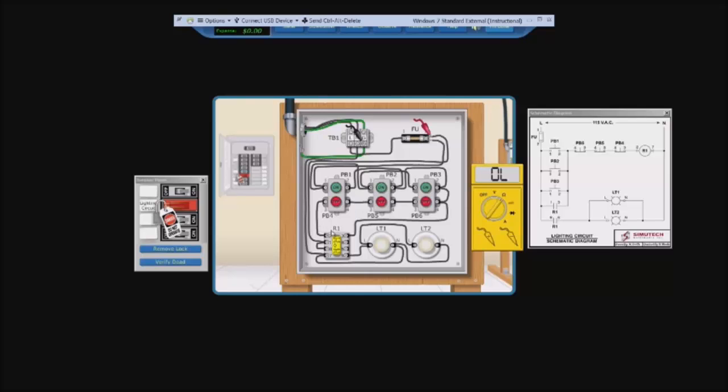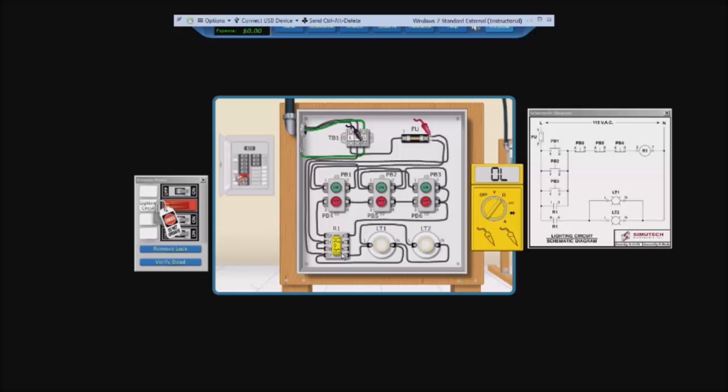Because it's going straight to 1, which jumps over to 8. And if we look on our schematic diagram, we will see 1 here and then 8, meaning that it jumps power to here, which goes through to 3, then comes to here, which jumps over to 6. So we shouldn't get a resistance reading there.